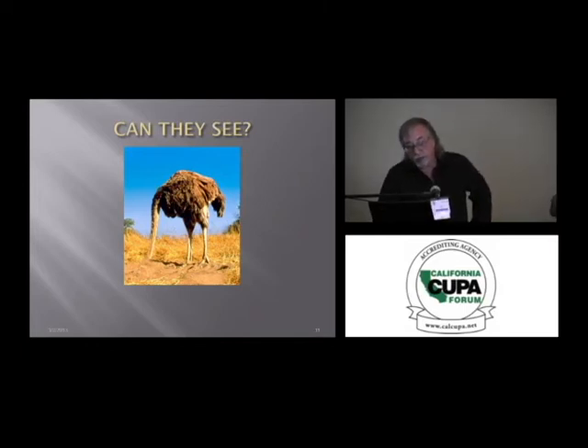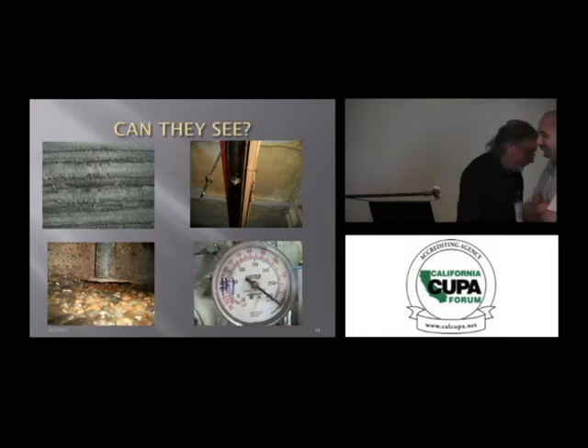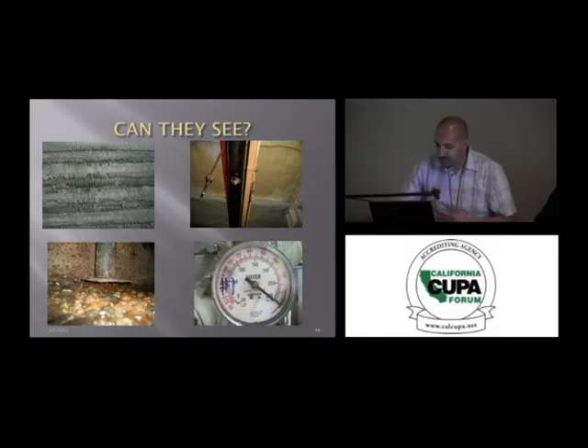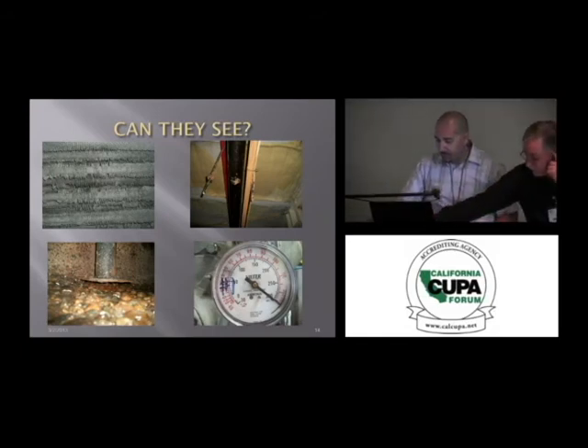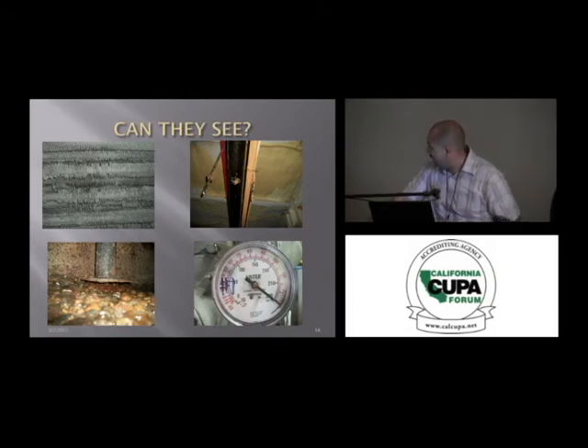This is an example of a nameplate that was missing on a vessel. The vessel's been there forever. We took some of the insulation off and it was fine. And the local AHJ was okay with that because the vessel's been in there for 20-some years. You see any green on a system out there? It's telling you something, okay? And then, of course, corrosion. Excessive ice buildup can cause small lines to break. Corrosion and erosion.